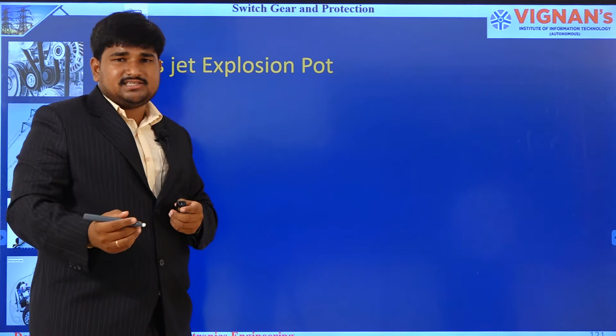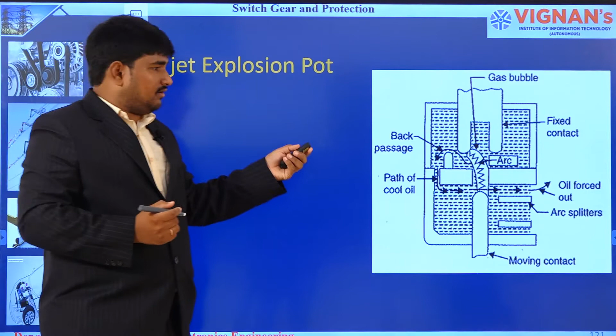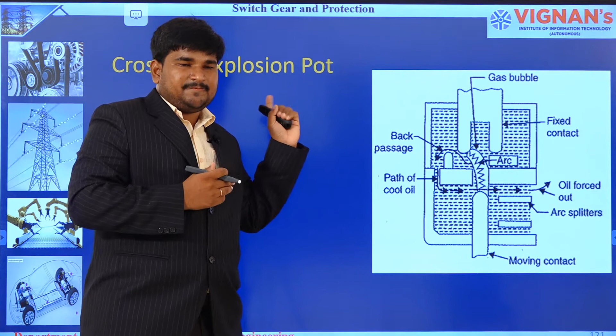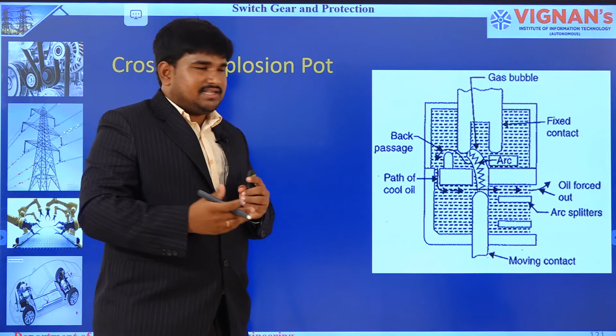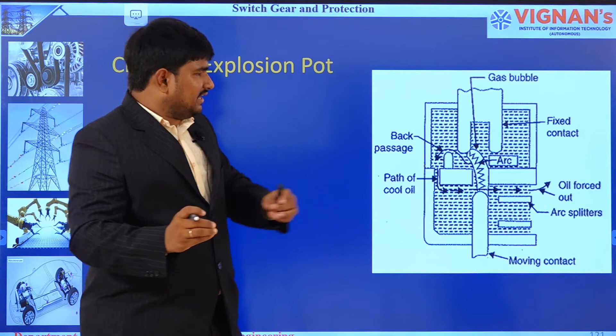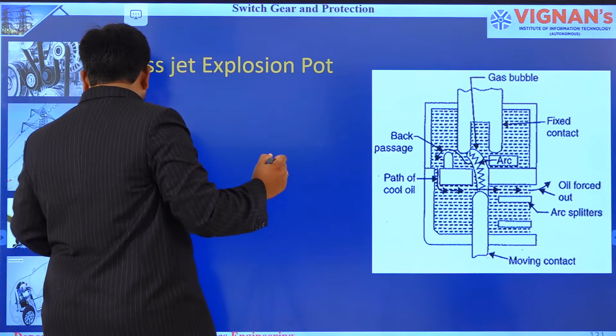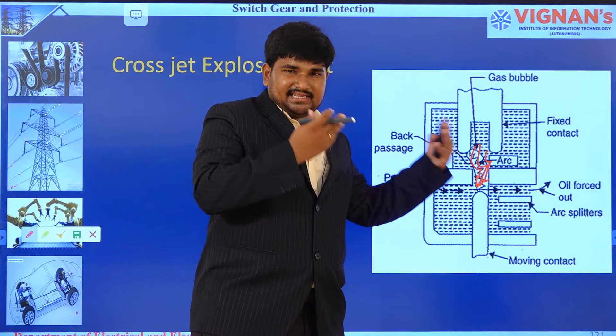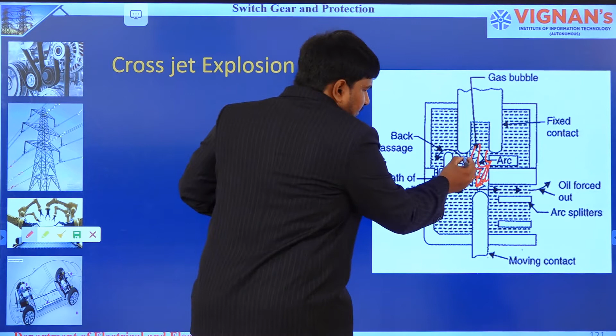The next type is the cross jet explosion pot. In the cross jet explosion pot, there is a special construction used to avoid the explosion of the previous case. In the previous case, with the plain explosion pot, for higher currents an explosion will happen because the chamber does not provide any path for the high pressurized gas. In this one, if you are using it for higher currents, even if the gas produced is increased, that gas will come out from these vents.